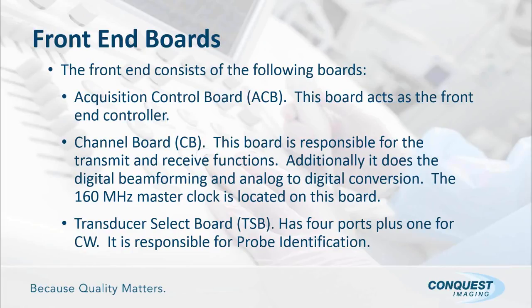When we're talking transmit, we're specifically talking about where the analog signal is introduced. So we're no longer talking digital information, we're talking analog, and we're talking high voltage. The transmit function generates that high voltage pulse that drives the crystals on the transducer. Then the receive function is where the echoes strike the crystals on the transducer. Those crystals generate tiny electrical pulses, and the receive function simply has to take those tiny electrical pulses, amplify them, and apply what we call time gain compensation. Time gain compensation is what the user sets up to adjust the amount of amplification based on the depth they want to look at. This provides a uniform image from top to bottom based on user input.